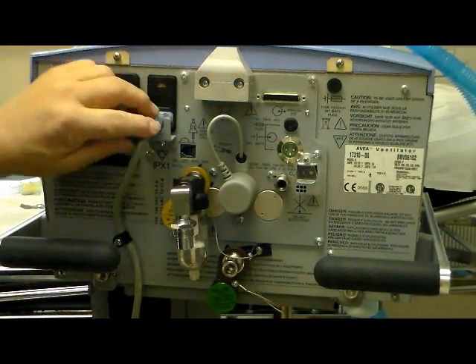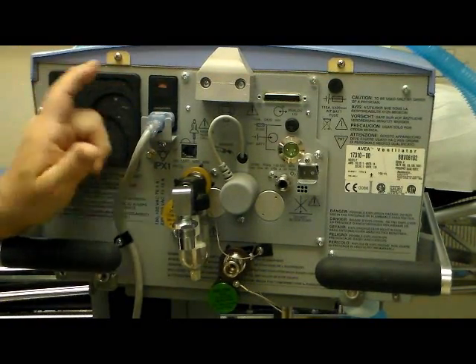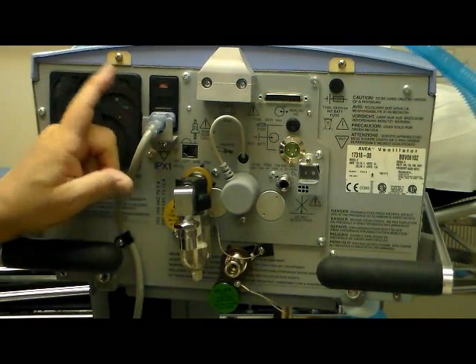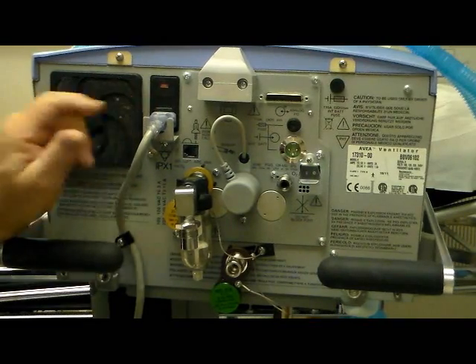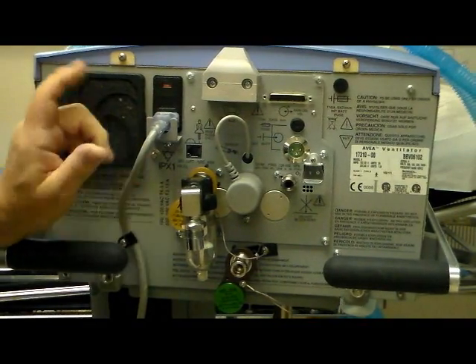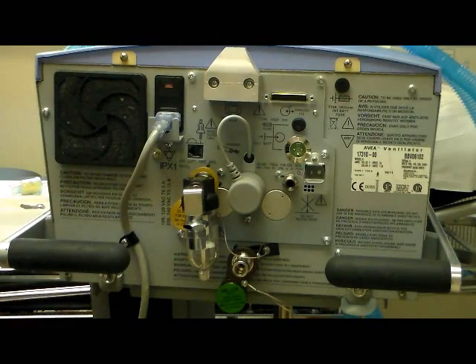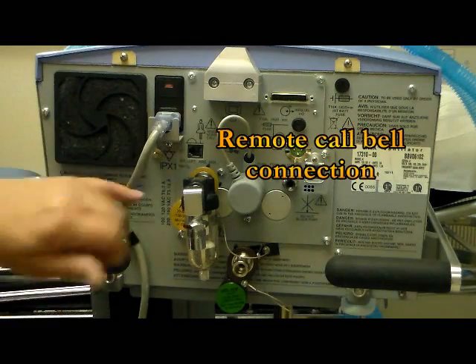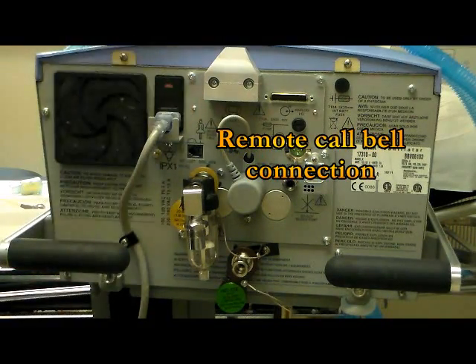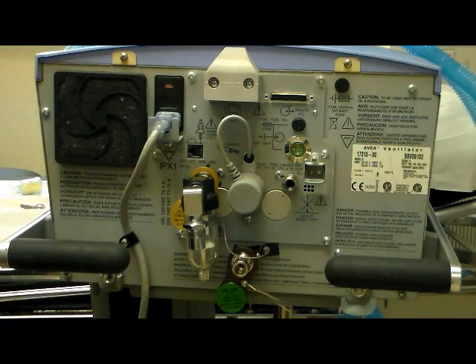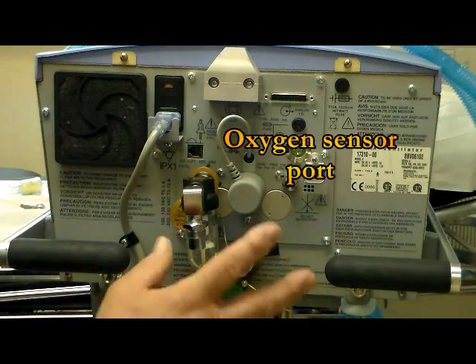Always with any ventilator, check, make sure this is plugged in, because in some machines, this could result in being disconnected and causing some problems, in that you won't be connected to the AC. Down here is a connection that you can configure this machine to have a remote call alarm. They call it a nursing call, but that's okay.